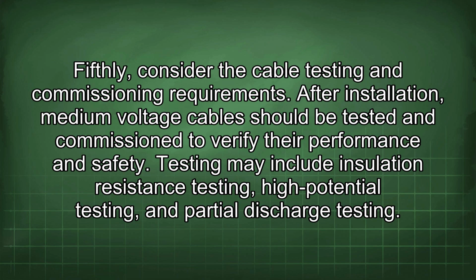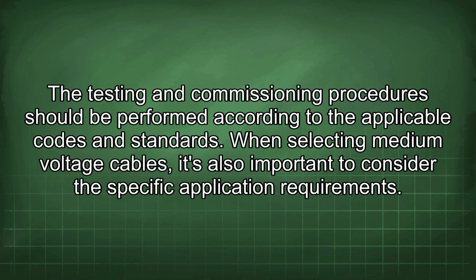Fifthly, consider the cable testing and commissioning requirements. After installation, medium voltage cables should be tested and commissioned to verify their performance and safety. Testing may include insulation resistance testing, high potential testing, and partial discharge testing. The testing and commissioning procedures should be performed according to the applicable codes and standards.